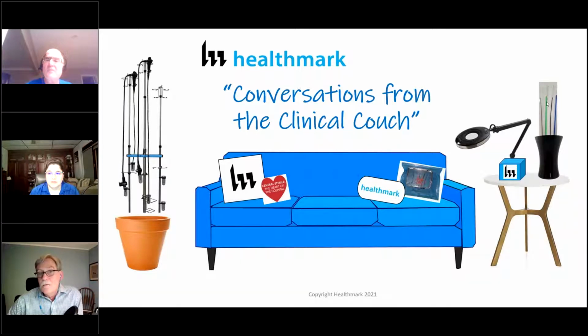Another nugget that is going to be, depending on the facility, a potential big transition is reinforcing that automated high-level disinfection is the best practice, no longer manual high-level disinfection. And that's also reinforced in the multi-society guidelines too. AORN has had that for a couple years. They recommend against manual disinfection. So we've really upped our recommendations on that stance too.